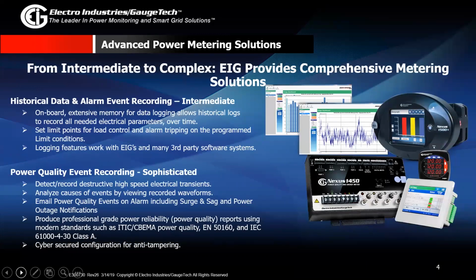Now coming to our Nexus line of meters, the Nexus series usually has a lot more capabilities as compared to our Shark series. Our Shark series ranges from very simple applications to more sophisticated. The Nexus, in comparison, really starts off at the intermediate level. Even a very basic Nexus meter will have very high-end capabilities such as onboard extensive memory for data logging, which will let you record all of your electrical parameters over time. So you can go back and look at what your data was last month or last year. The meters can record data for over several years because they have extensive memory on them. You can set limit points and alarms to get information on your power quality. And you can also integrate it into any third-party software system that uses Modbus, BACnet, or DNP3 to talk to these equipment.